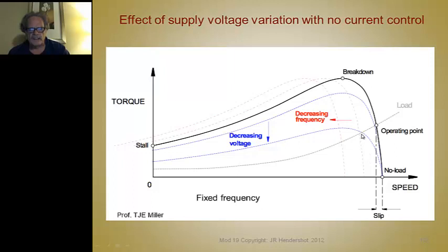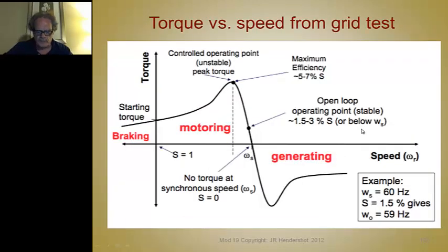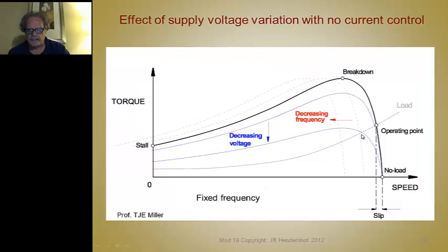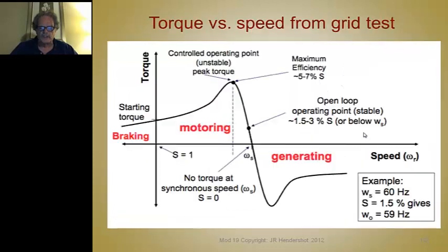So there again, with the same load, with the decreased voltage, you'd be operating at these 2 points here. But with an inverter control, you can control both of these. So as we'll see, we're going to define an envelope that a machine and an inverter together will run with.